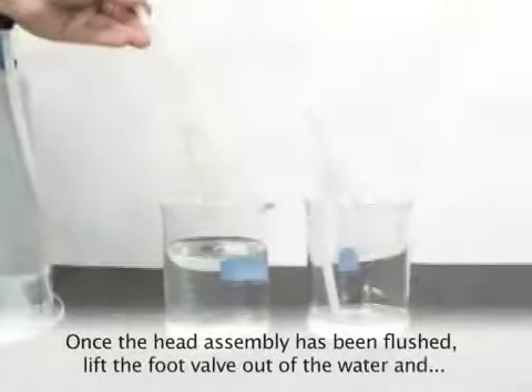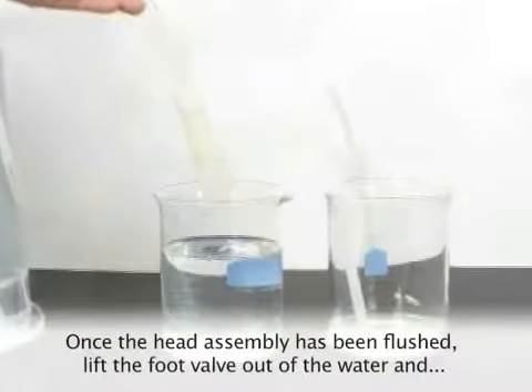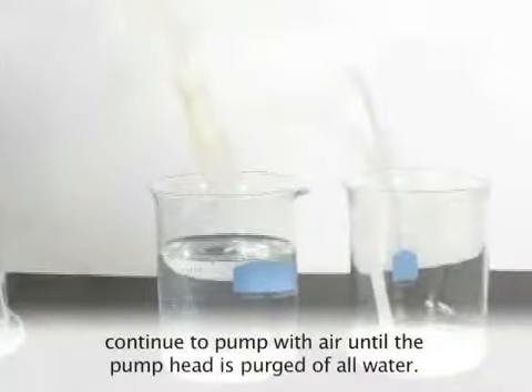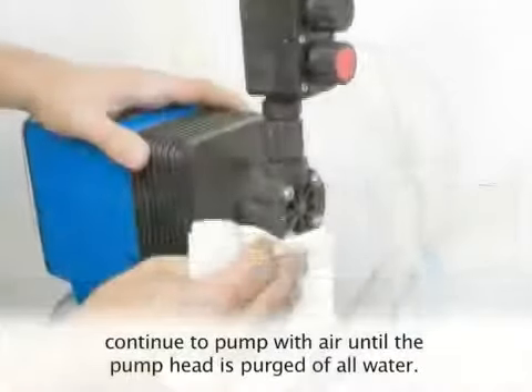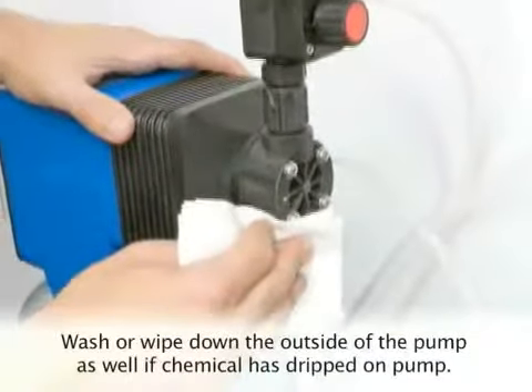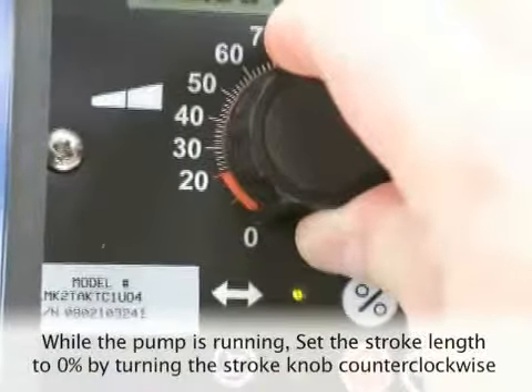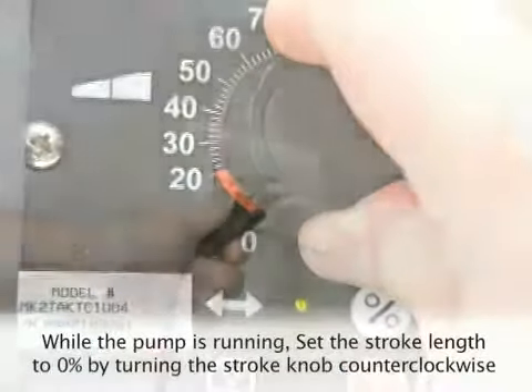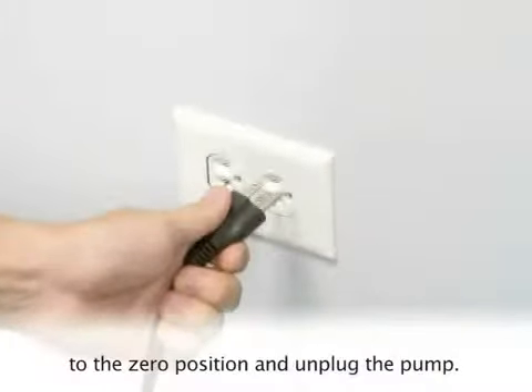Once the head assembly has been flushed, lift the foot valve out of the water and continue to pump with air until the pump head is purged of all water. Wash or wipe down the outside of the pump as well if chemical has dripped onto the pump. While the pump is running, set the stroke length to 0 by turning the stroke knob counterclockwise to the 0 position, and then unplug the pump.